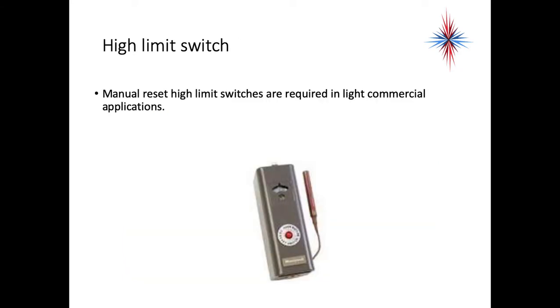High-limit switches with manual reset are required in light commercial applications. If the boiler temperature gets too high, it needs to cut off and require a manual reset. We have high-limits that are part of the aquastats as operating controls, but if that high-limit fails, many light commercial applications require a second manual-reset high-limit.